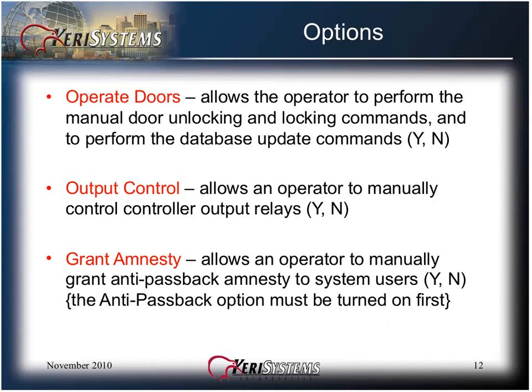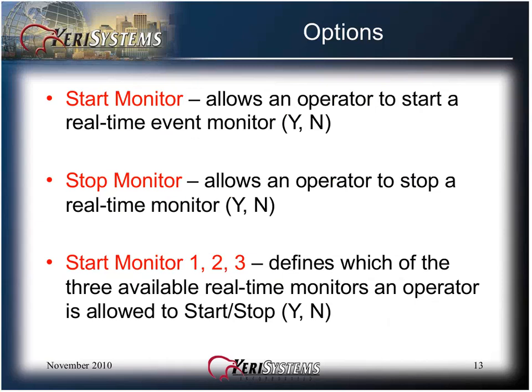Operate Doors allows the operator to perform the manual door unlocking and locking commands, and to perform the database update commands. Output Control allows an operator to manually control controller output relays. Grant Amnesty allows an operator to manually grant anti-passback amnesty to system users. The anti-passback option must be turned on first, and anti-passback is taught in its own separate KTI module. The Start Monitor option allows an operator to start a real-time event monitor, and Stop Monitor allows an operator to stop a real-time monitor. Start Monitor 1, 2, and 3 defines which of the three available real-time monitors an operator is allowed to start or stop.